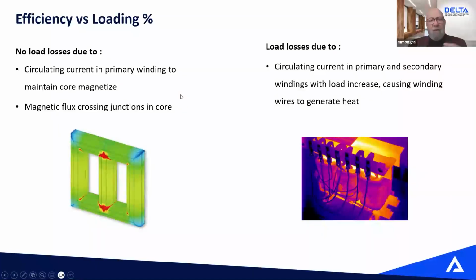Losses in a transformer, there are two types of losses: no load losses and load losses. The no load losses, it's the core. It's strictly your core and your excitation current circulating in your primary winding to keep that core magnetized. And you're stuck with them. You energize a transformer, there's nothing connected to the secondary or grid side or inverter side, there's going to be some losses in the transformer, and you're stuck with them. And then the load losses are the losses in the winding.